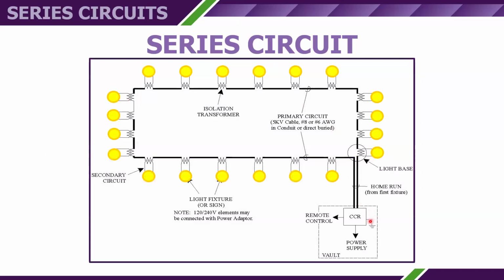So we're back to our constant current regulator and our series circuit. It's not truly a series circuit like Christmas tree lights, where if you lose one light, they all go out. Airfield lighting has the L-830 isolation transformer, which is right here. Your primary loop from the regulator goes through the primary coil on the L-830 transformer. The secondary coil on the L-830 transformer is what powers the light. So if there's a light open circuit, your primary series circuit is still continuous.